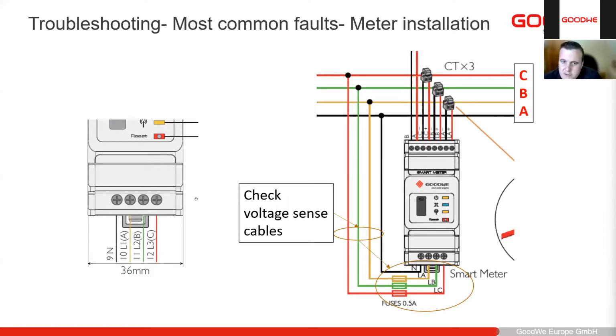And if we swapped two of these on the inverter, we need to swap both the voltage sense and the CTs around to make sure that is correct. So what happens if you put the voltage sense incorrectly? If we put phase 3 here instead of phase 1, this CT here is reading the wrong readings. It will essentially read the current out of step and see it as a reverse direction.